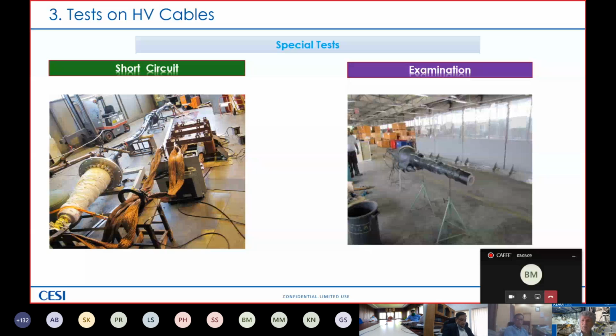Then I also put examination, because examination is very important for whatever test we are talking about. Type test, pre-qualification test, explosion-proof test, pollution test, short circuit test. At the end of the test, of course, it's a must to fulfill the requirements of the test, but also the examination should not present any deterioration that can create problems during normal operation. This is a very short sentence, but very dangerous, because without any example, you can start a discussion with the inspector who witnesses the test, and you are lost.